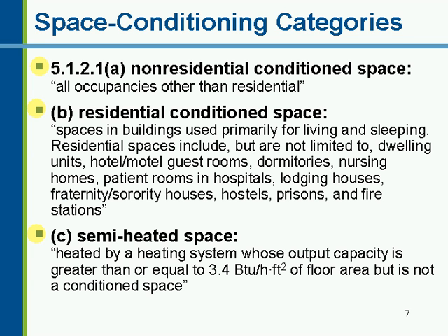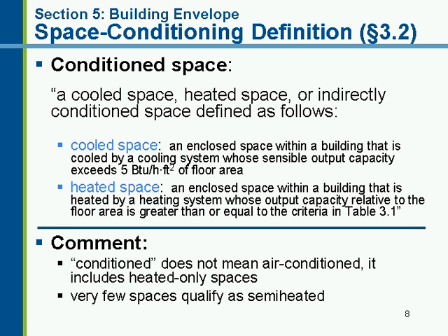Now, if we drill down a little further into this, a conditioned space is considered a cooled space, a heated space, or an indirectly conditioned space. So be note that a cooled space is anything that has a cooling system with an output capacity greater than 5 BTUs per square foot of floor area. So you compare that with the 3.4 on the previous page, you see there's not much of a difference there.